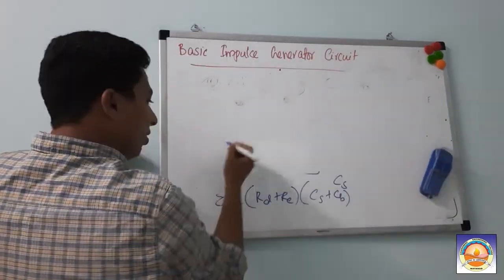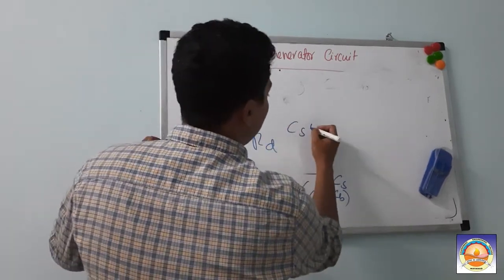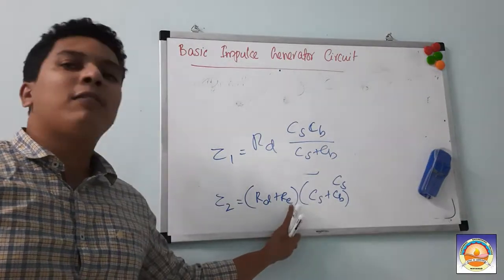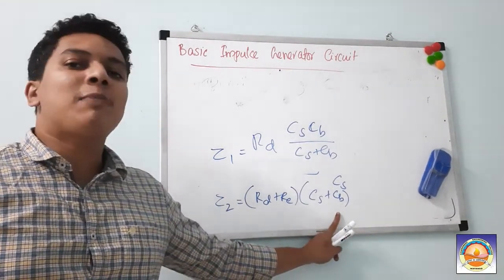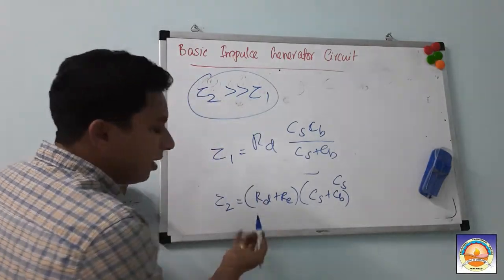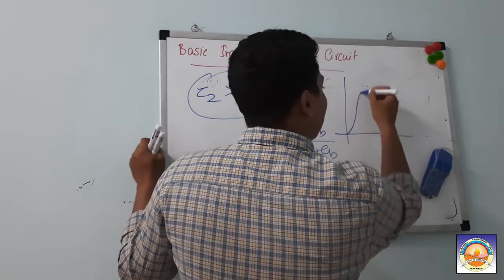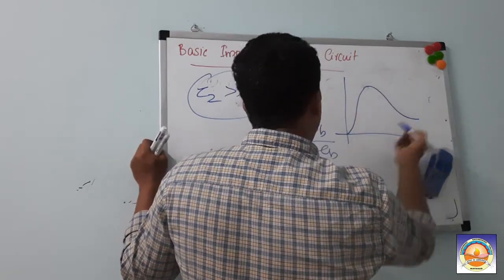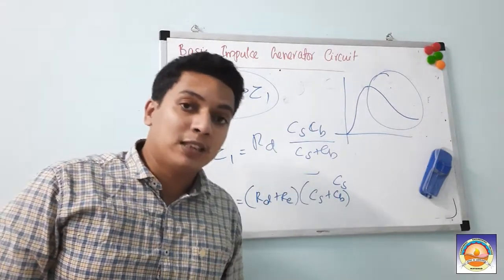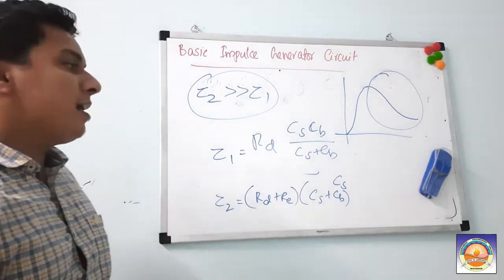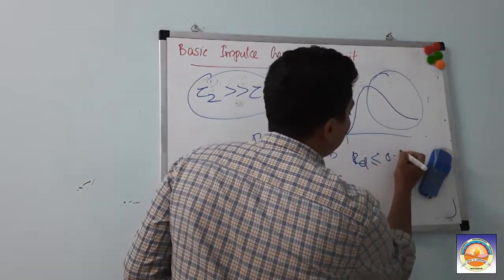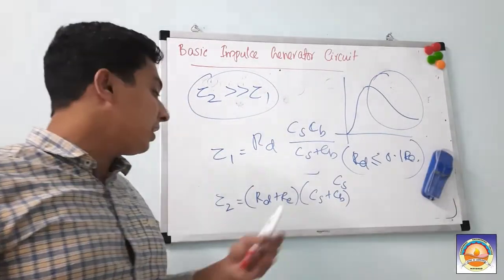The first part of the impulse waveform is created during the charging process with a smaller time constant tau1, and the tail part during discharging with a larger time constant tau2. You can control both time constants by adjusting Rd and Re values. The important factor is that Rd ≤ 0.1 × Re.